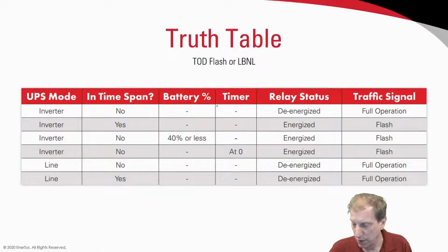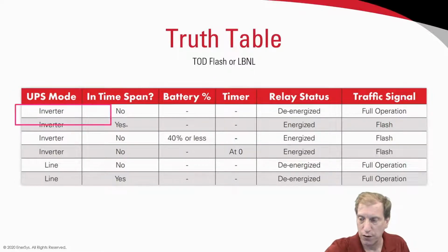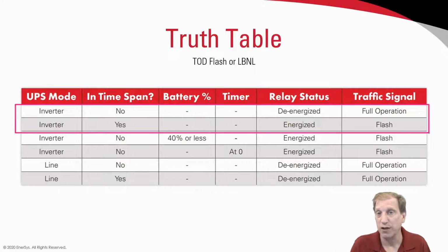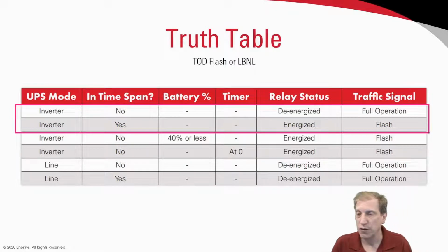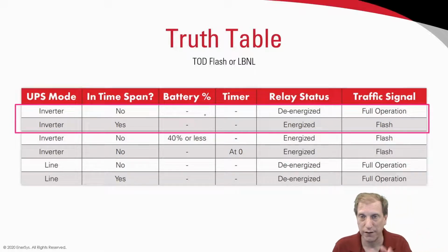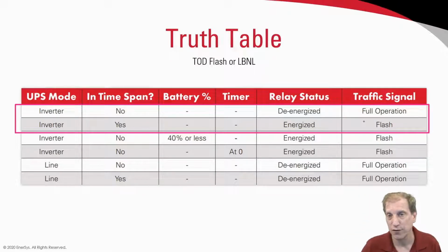All right, so the first two right here are all about the time of day part of this, right? As we look at it, we'll say in inverter mode, are we in the time span? No. So we're not going to go to flash. We're going to be in full operation. We don't care about battery and we don't care about timer because we're just looking at the time of day. That's it. Second one, inverter mode. Yep. Time span, yes. So then we are for sure going to flash, right?